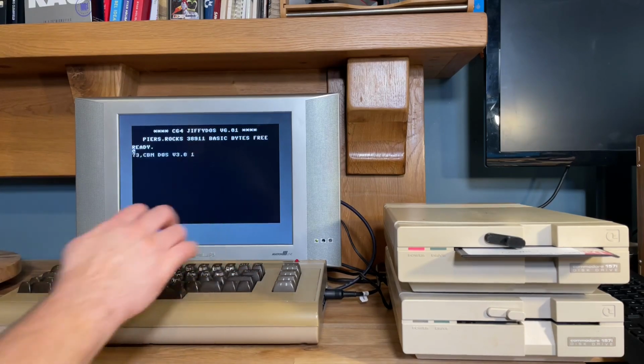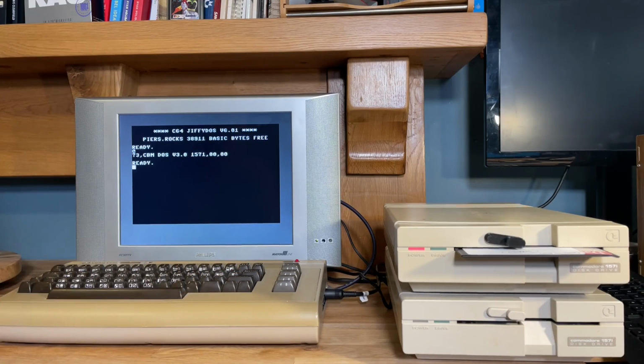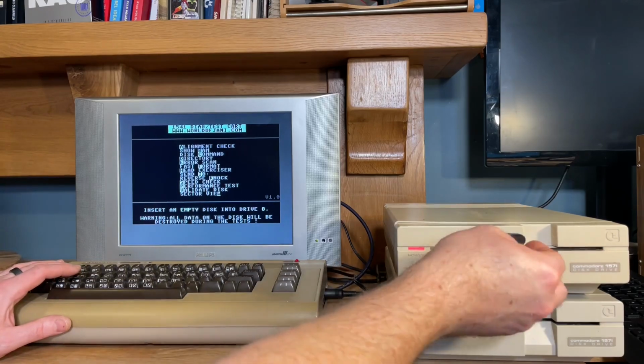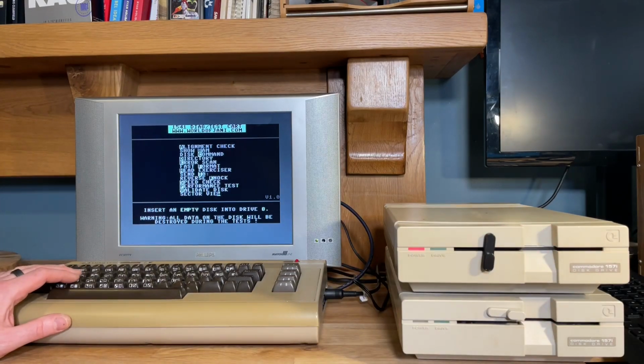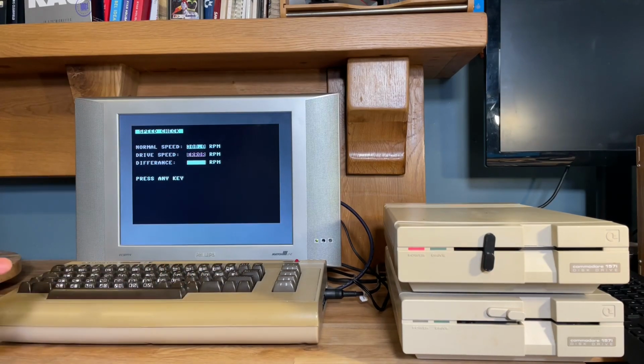Okay, so we can communicate with the drive, but I'm not expecting anything else to work, as the spindle motor is not turning. We discovered that previously. Just to prove that it's not working, do a speed check. Just get an error straight away. It's because the motor is not turning. So we will need to diagnose that problem next.